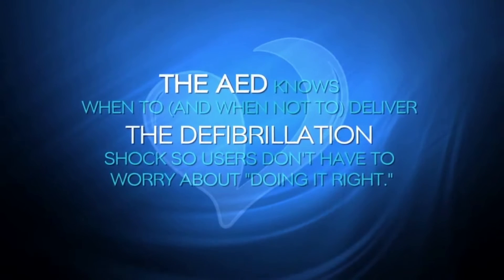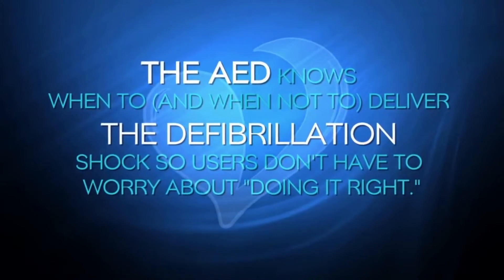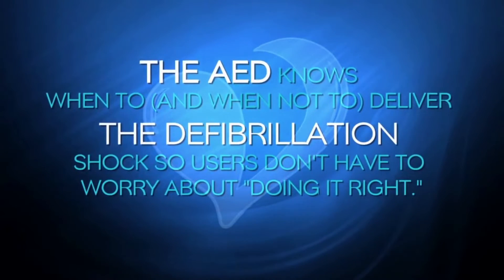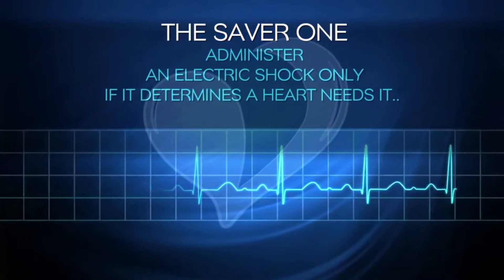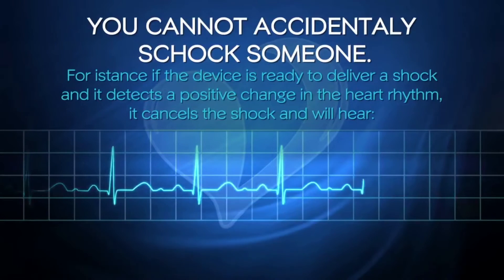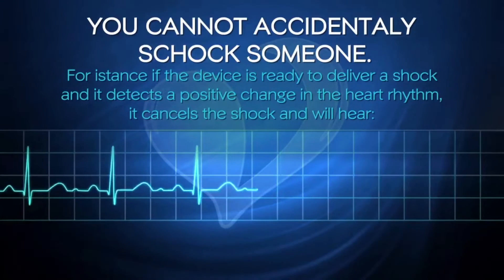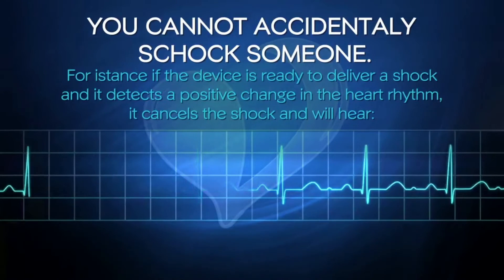The AED knows when to and when not to deliver a defibrillation shock, so users don't have to worry about doing it right. The Saver One administers an electric shock only if it determines the heart needs it — you cannot accidentally shock someone.